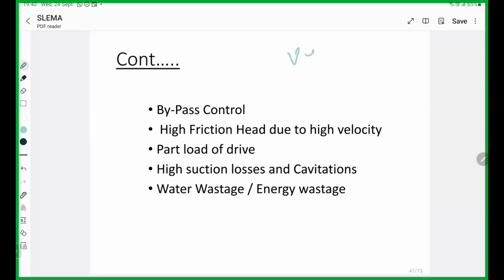VFD is a good option, ideal for a closed system. That means it is not applicable to a flat system curve. It should be for this closed system, like a VFD application.